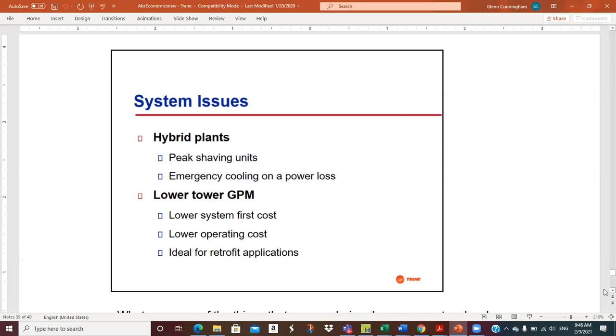And so, with the power out, if you've got a centrifugal chiller, that's a 600, 800 kW load. That's a lot on your emergency generators. But if you have an absorption unit, guess what? If your boiler's burning natural gas and you're making steam or hot water, the natural gas keeps flowing. The gas is going to be there, and the amount of power it takes to run your boiler or a direct fired chiller is nothing. You're talking 20, 30 kW, which is easy to pick up on the emergency generator. The biggest load then is your distribution pumps. Make sure you can distribute it through the building.